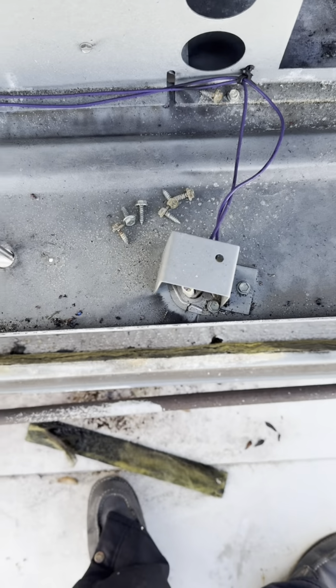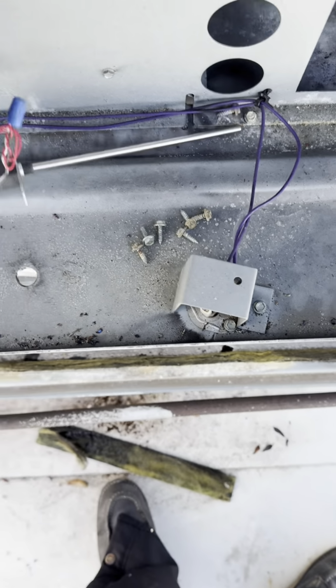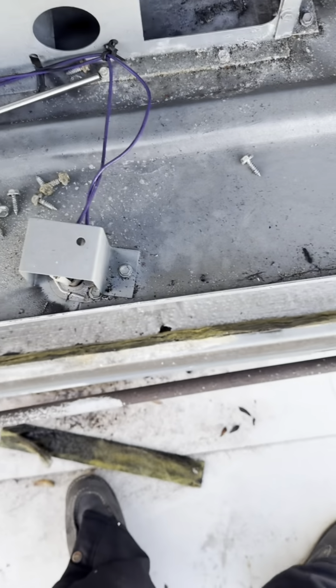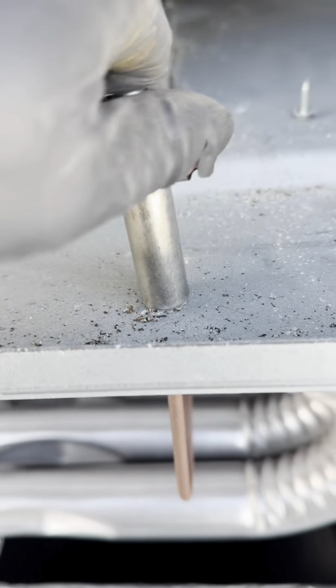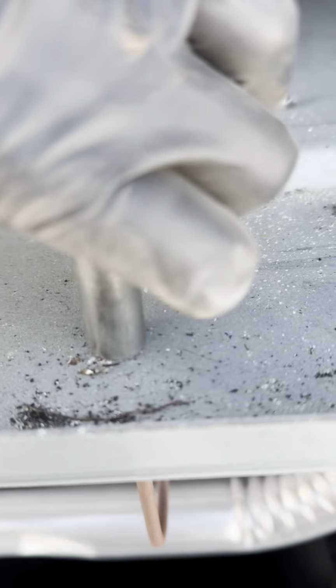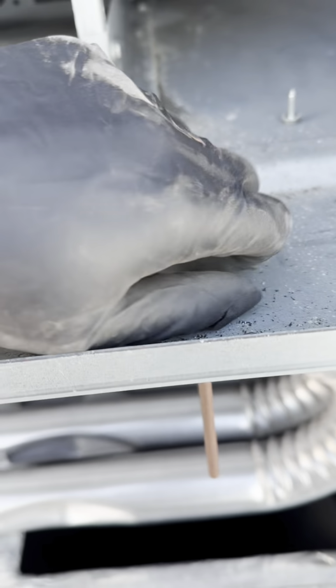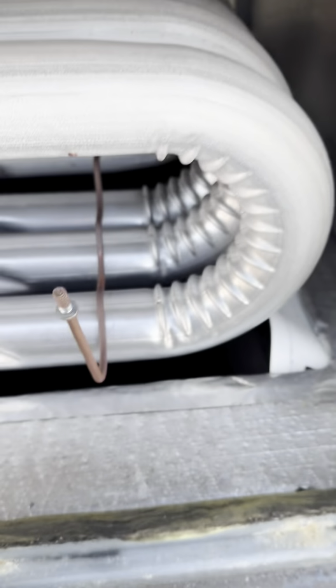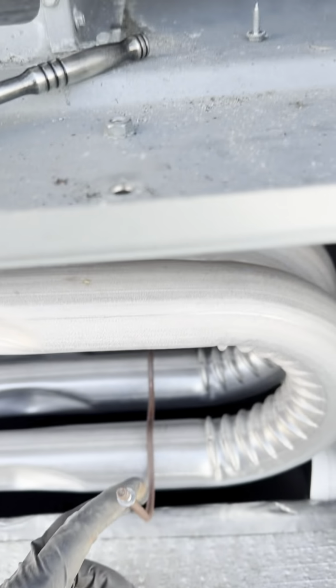Slide the discharge air sensor out of the way gently, and then begin by removing the support bracket right here with a 7/16 ratcheting wrench, any 7/16 wrench. Remove this bolt so you can drop the bracket. Okay, after removing that, I normally let it just hang there. I don't take the other side off.